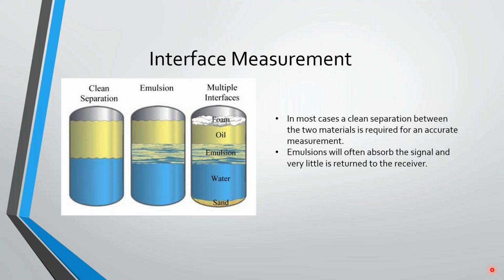Perhaps we've got oil on water, which is a very common one, right? So we've got some kind of separator system and then oil on top of water. We want to pump out the water, but we want to stop pumping as soon as we get to the oil. Being able to determine that interface with this device, the device can then send a signal to our pumping system and shut it off once we've pumped all the water out and we reach the oil.